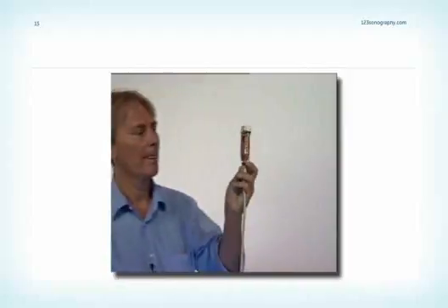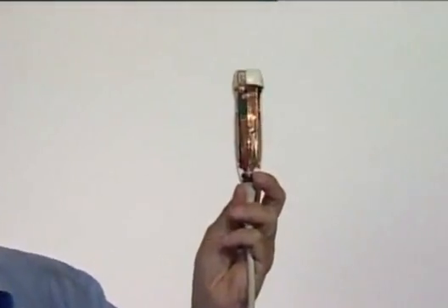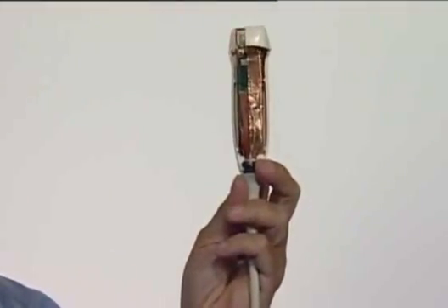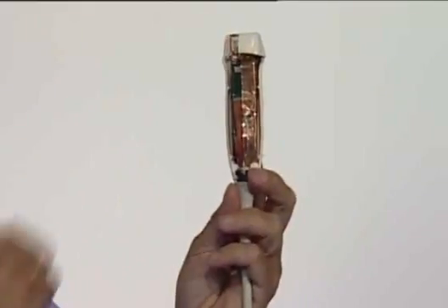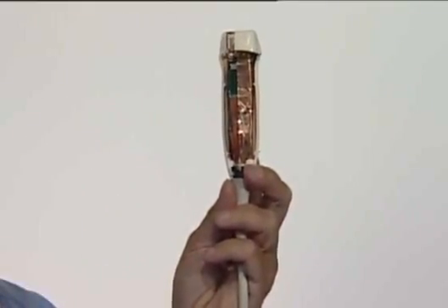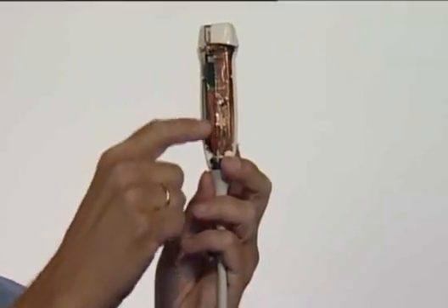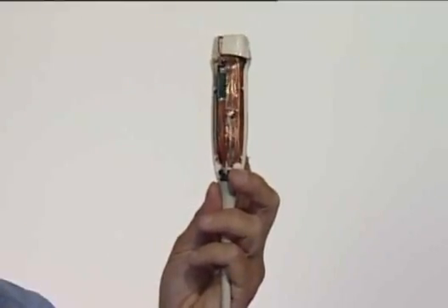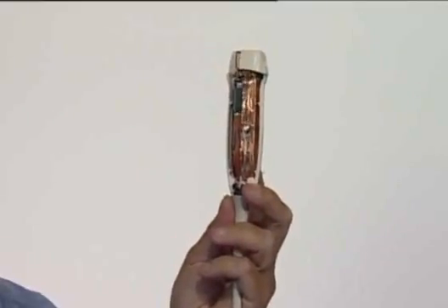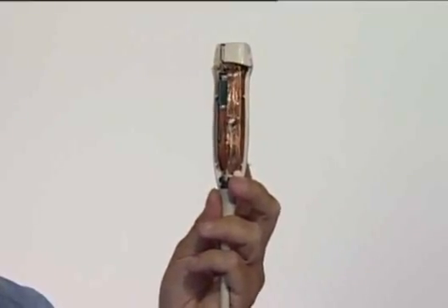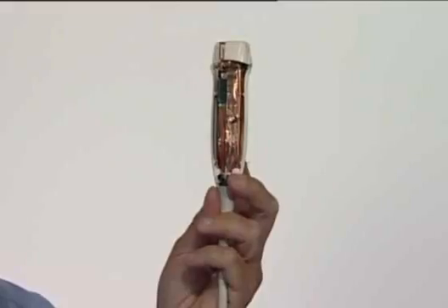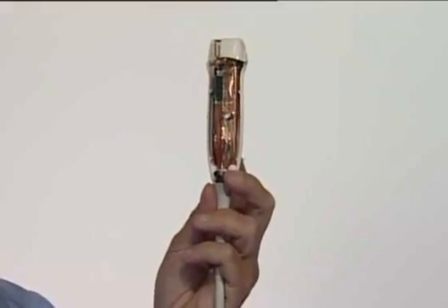Have you ever asked yourself what is inside a transducer? Well, I can tell you. A lot of very thin wires and cables which are attached to the transducer elements which are somewhere up here. You have some dampening up here for the crystals, and then you have all sorts of other electronic elements which honestly I don't even know what they are. But keep this in mind when you have these transducers in your hand, because if you drop them and they break, they're very expensive.